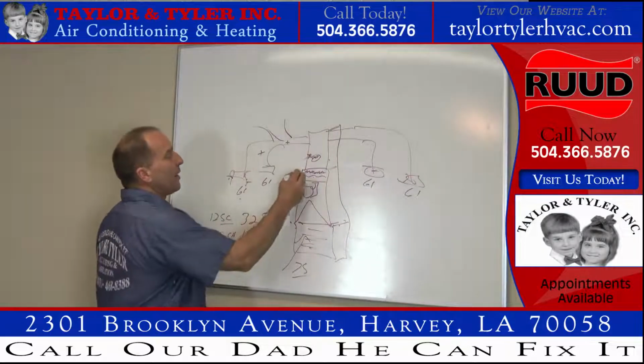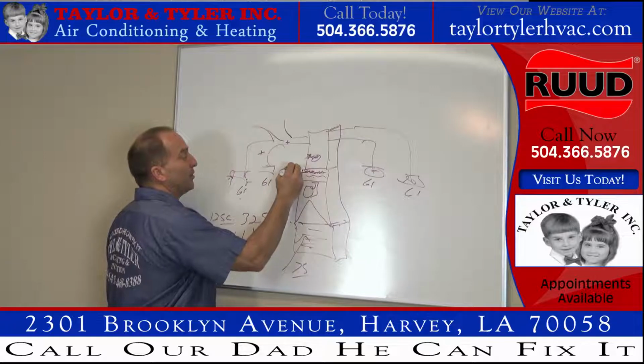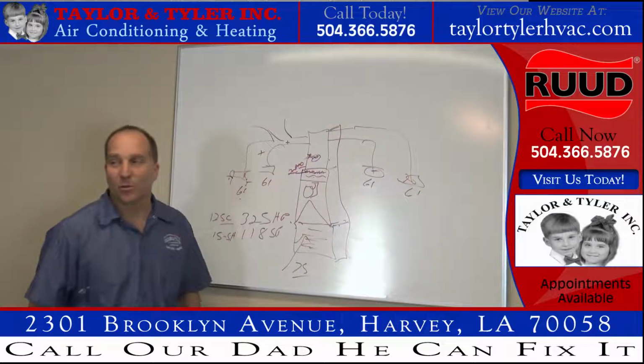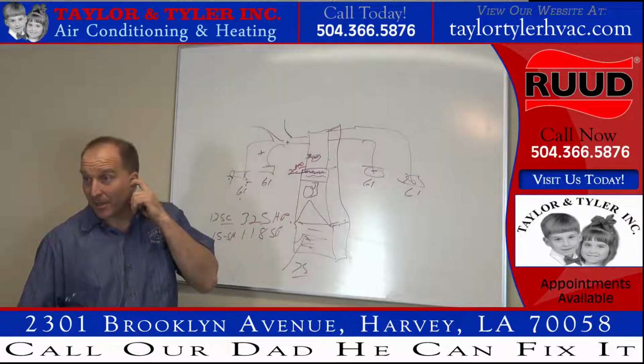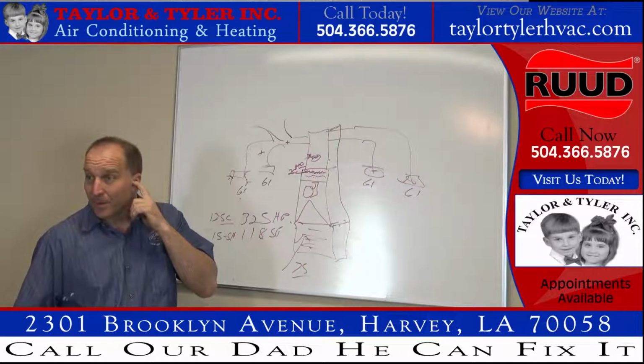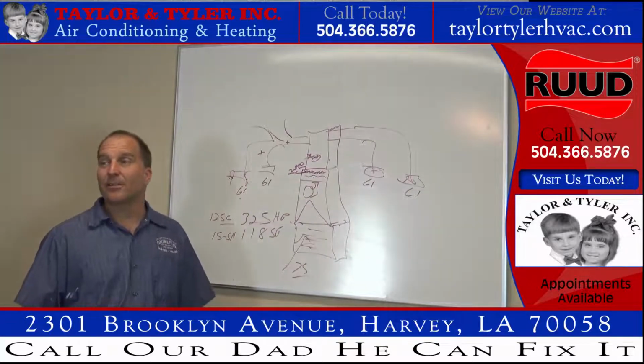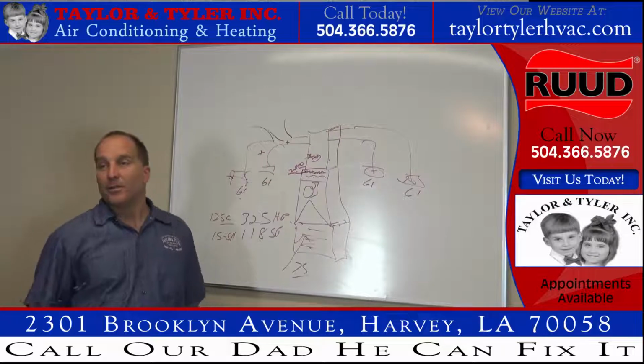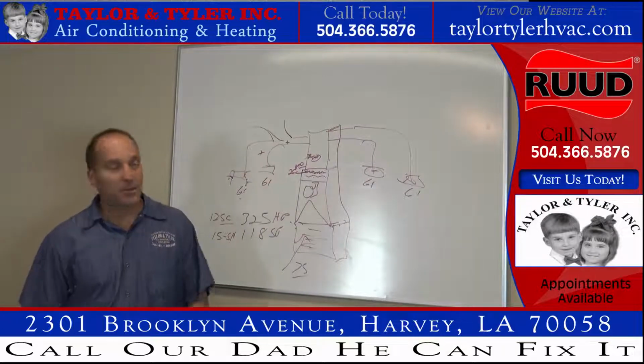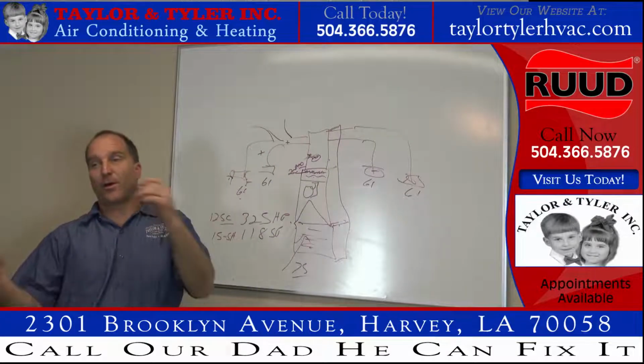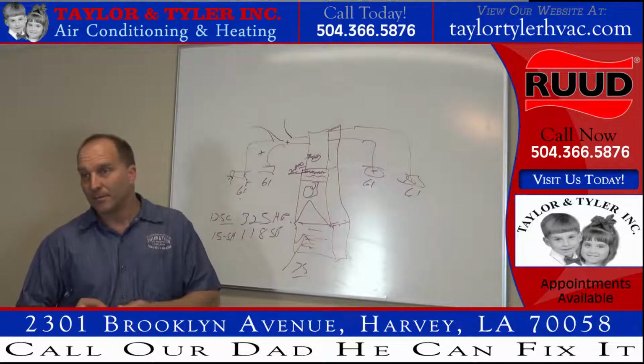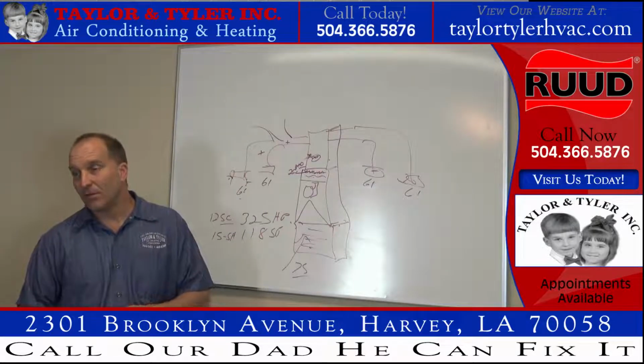Well, how about 20 amps right here driving the energy bill up? Non-stop 20 amps, isn't it? It keeps heating the air up, so it makes the air conditioner run all the time. So the air conditioner draws 15 amps, plus another 20 amps, you're drawing 35 amps all the time. You got a $400 energy bill.